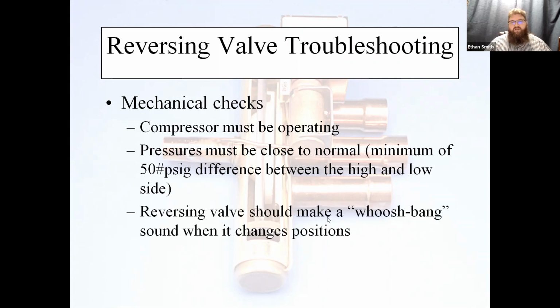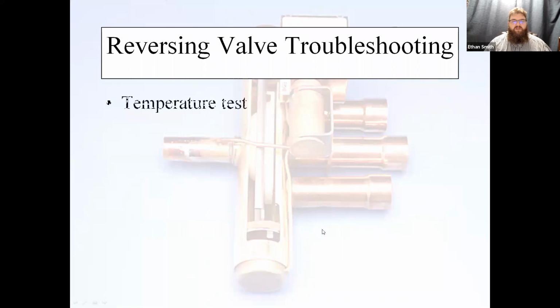Okay. When you reverse cycles on the reversing valve, you can do that simply by applying or taking power away from that reversing valve solenoid. You should get that whoosh-bang sound as it changes positions. And that's simply the refrigerant equalizing between the high and low side as that thing moves over. That moves that clamshell over.